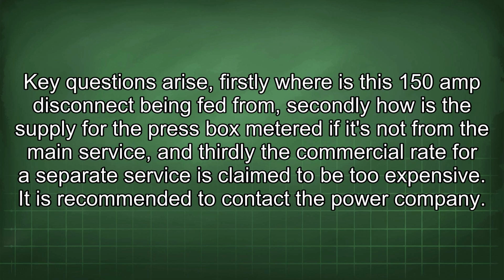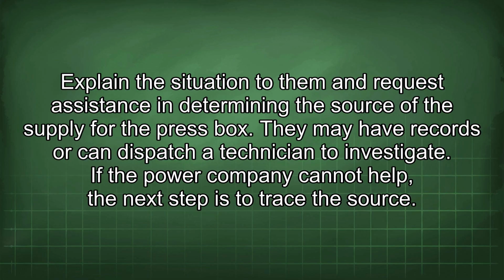Key questions arise. Firstly, where is this 150 amp disconnect being fed from? Secondly, how is the supply for the press box metered if it's not from the main service? And thirdly, the commercial rate for a separate service is claimed to be too expensive. It is recommended to contact the power company, explain the situation to them, and request assistance in determining the source of the supply for the press box. They may have records or can dispatch a technician to investigate.